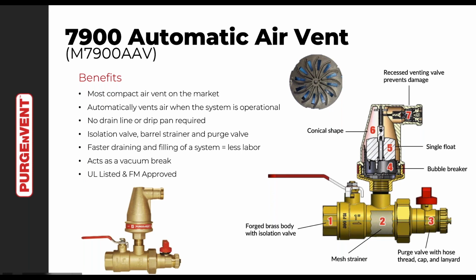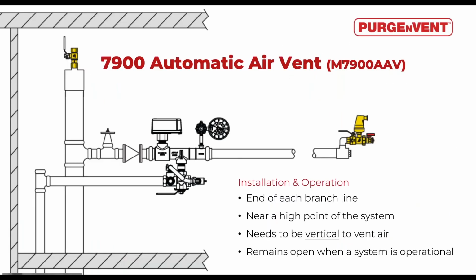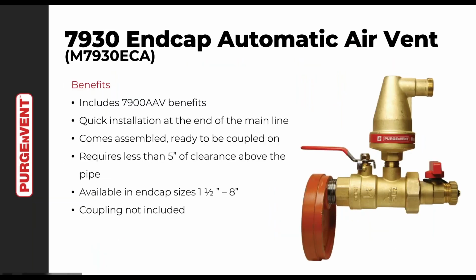And then this valve feeds up to the 7900 automatic air vent. This conical shaped unique air vent has a float mechanism inside it, and the unique feature of this thing is the bottom of it. We call it the bubble breaker. The propeller-like device here that you see has slits in it that takes the large air volume and breaks it into smaller air bubbles that go around our float mechanism. And once water comes up underneath our sealed chamber here and pushes up on that housing, that pulls down on a linkage in the center of our unit, which closes off the air vent. So we don't have any type of dripping or spitting of water or moisture in our device. We typically see these again located at the end of lines or at the top of risers.